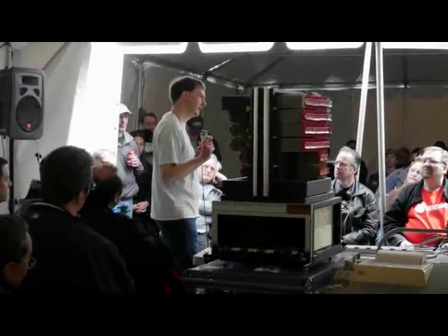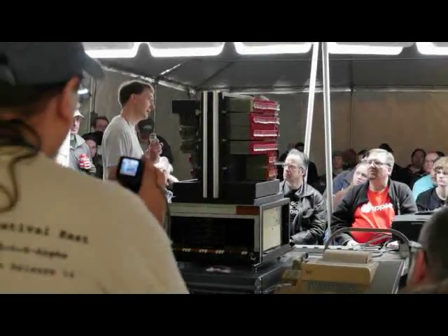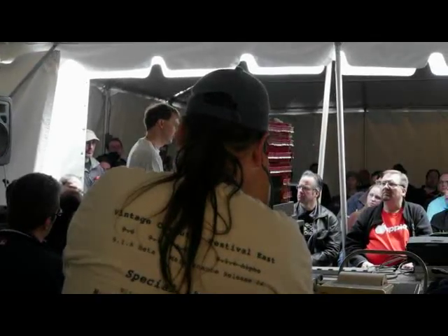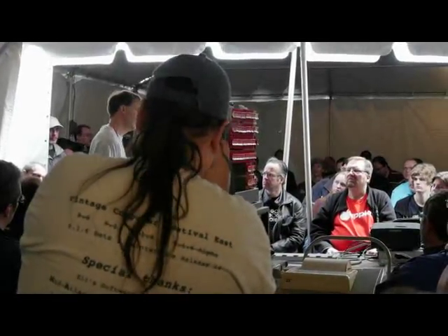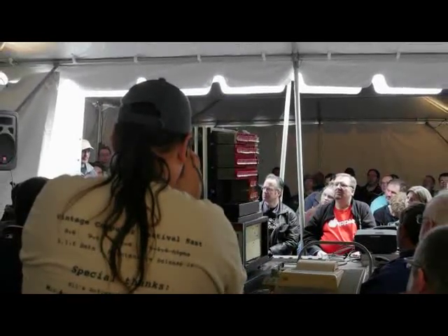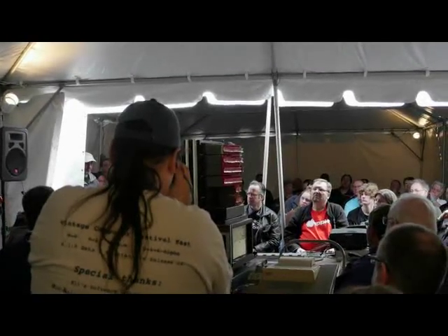So I retained them. There is one issue with them. There is some cracking around the terminal where the aluminum is corroded, which may make a long-term issue with it. If I open the seal, there's a liquid electrolyte in them that, if it evaporates, will make them go bad. So we will need to monitor them. The easy way to monitor them is just measure the ripple periodically. If the ripple's starting to get worse, then you know you have a capacitor going bad.